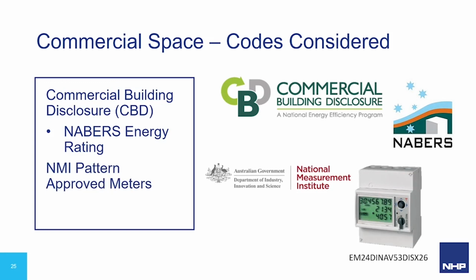Since the meters will be used for billing, they must be NMI approved meters. I didn't cover NMI previously because it isn't specifically to do with energy efficiency, but basically any utility grade meter needs to be tested and approved by a verifier before installation. This extra check ensures the meter remains accurate for its lifetime and isn't easily tampered with. These standards and tests are set out by the National Measurement Institute, the governing body that develops and maintains the Australian measurement standards.